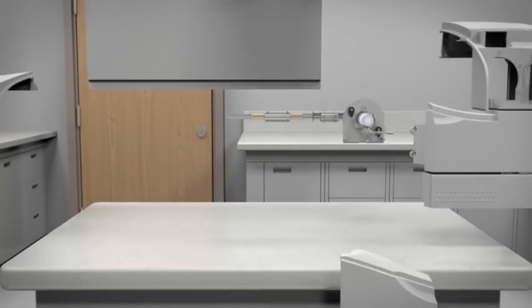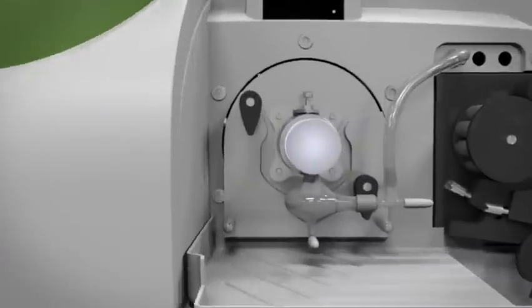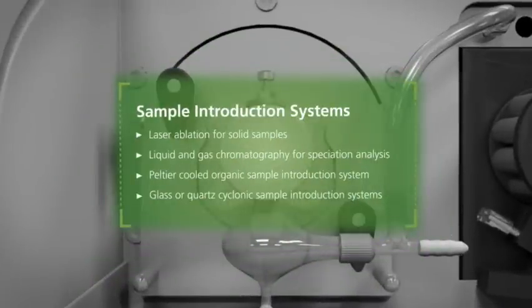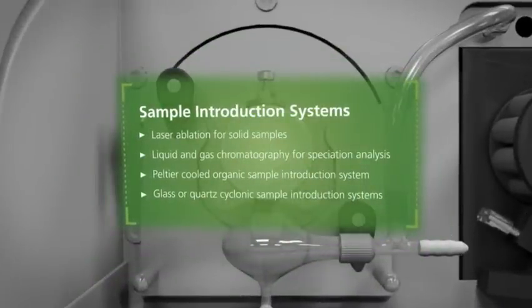One thing you'll notice at first glance is the large, open sample introduction area on Nexion. This design enables the instrument to accept a wide variety of sample introduction systems that can be quickly and easily switched out to suit a particular application. Once your sample is introduced and has been converted into a fine aerosol in the spray chamber, it passes into the torch and through the argon plasma.